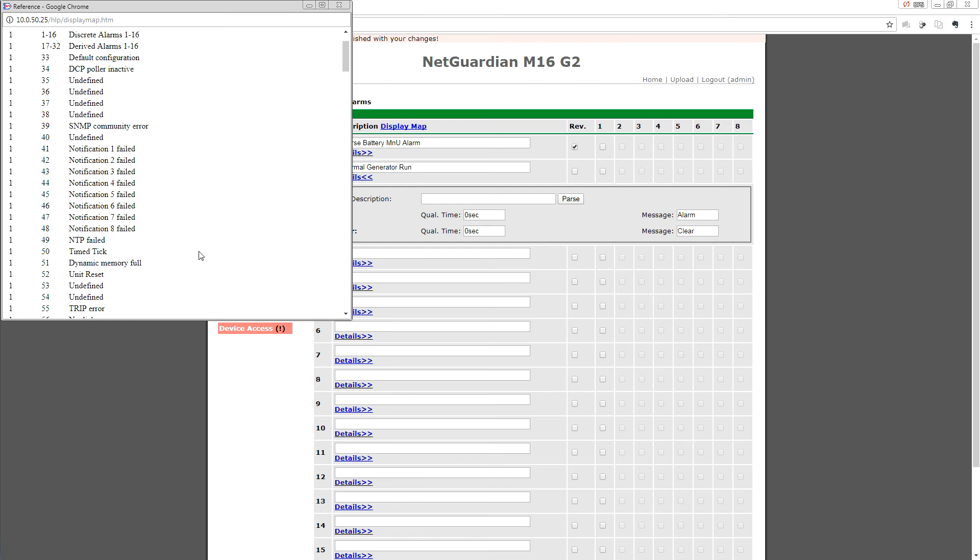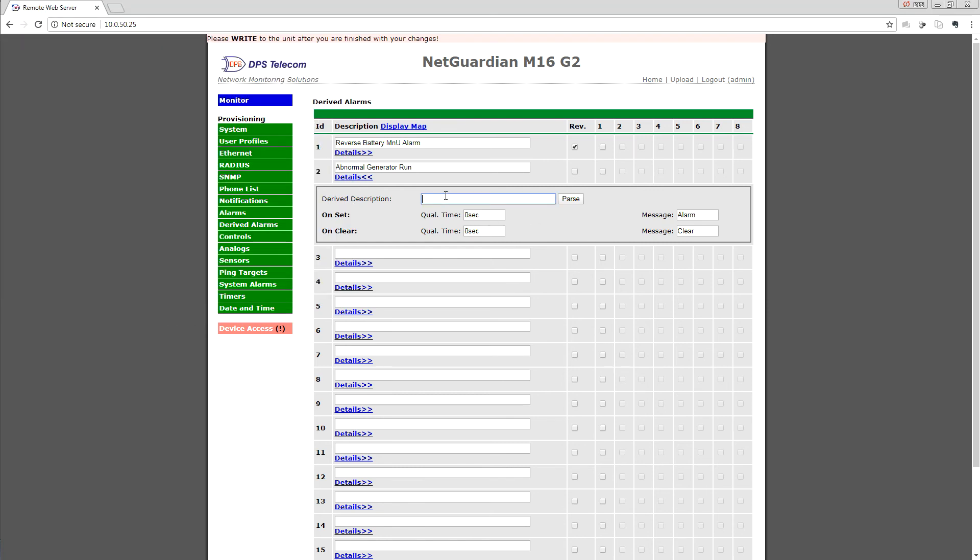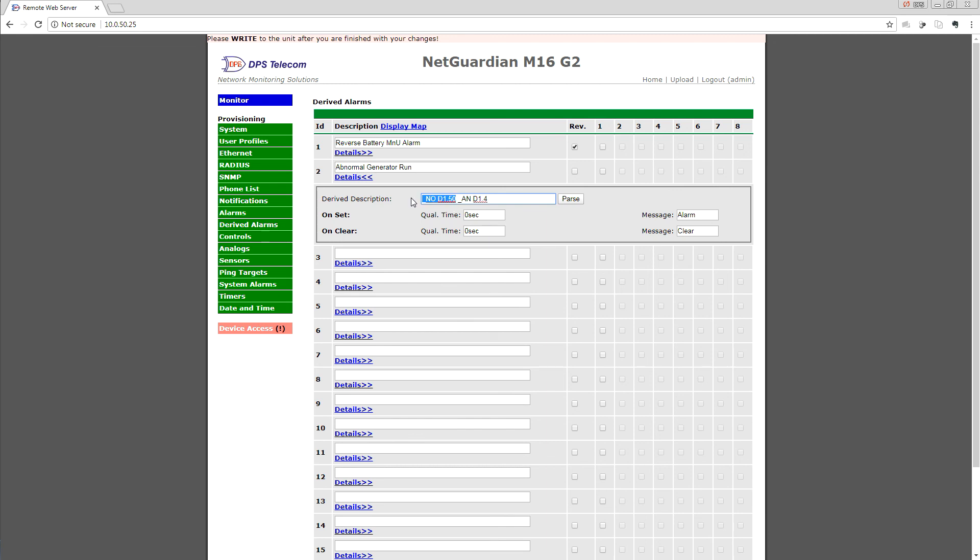So with those two in mind, we can now write an equation, and what we want to say is: each one of our commands here has a two-letter abbreviation. So this is NOT, so if NOT display 1.50, meaning if the time tick is not set, which by definition means we're outside of a one-hour window on Tuesday morning, AND display 1.4, and the generator is running, then throw this alarm. This is an abnormal generator run because we're not in the window and the generator's running.